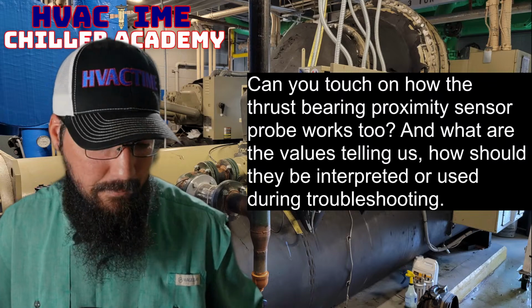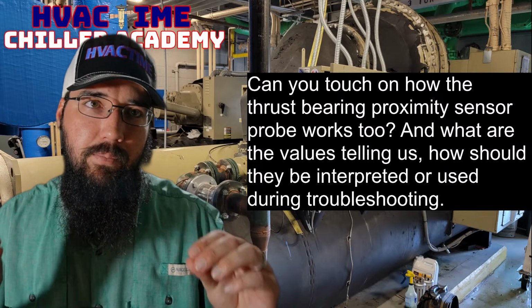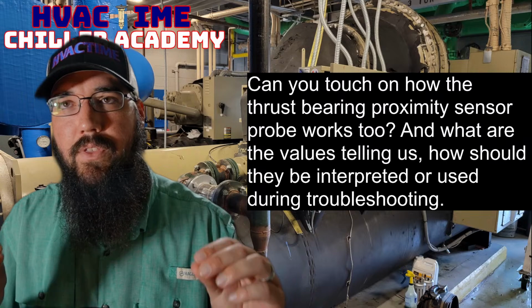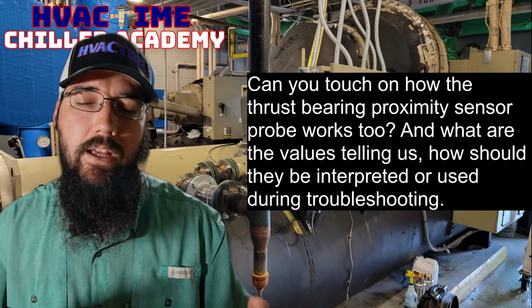Very similar. And here's the thing, while there may be specific things that are, say, York in what they're doing, they're not as proprietary as we think they are. A lot of these basic concepts are genuinely applicable across the board on different machines. They just have slightly different flavors on how they go about doing the same basic idea. They're still probably using a bull and pinion gear design, still probably using a helical gear design, and they're still trying to step up a single or low speed motor to a high speed impeller, whether it's a single or dual impeller design with a set of sleeve journal bearings.